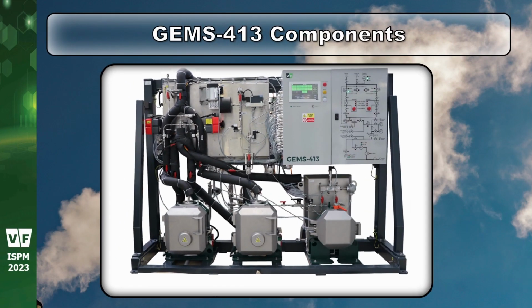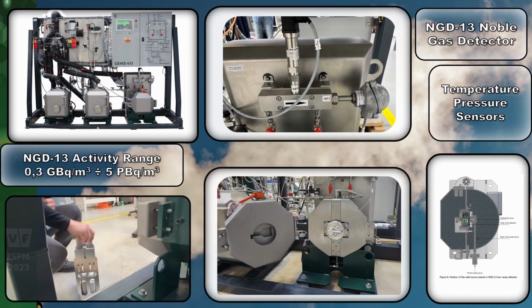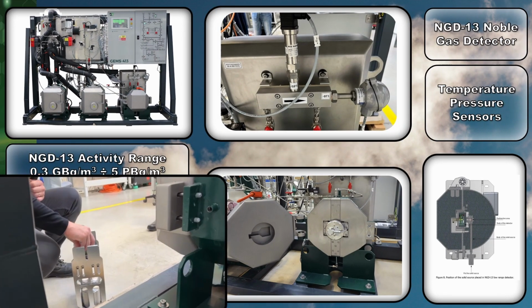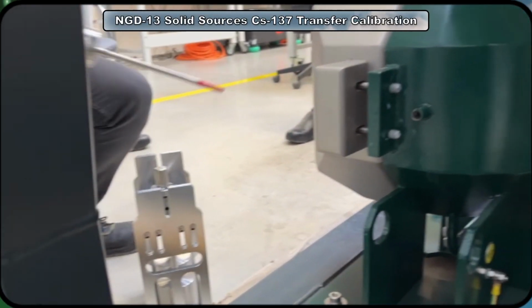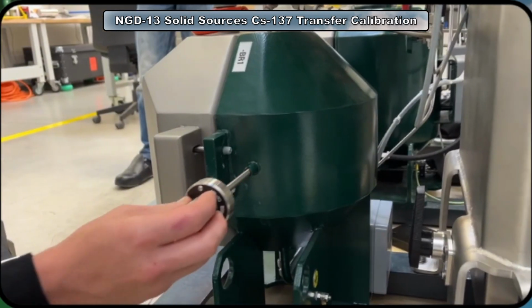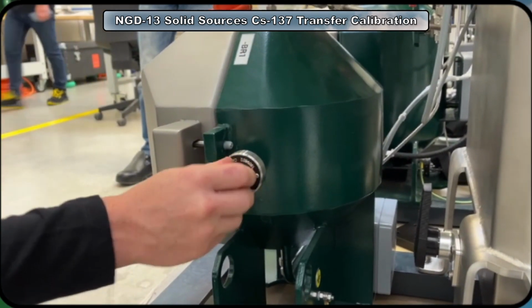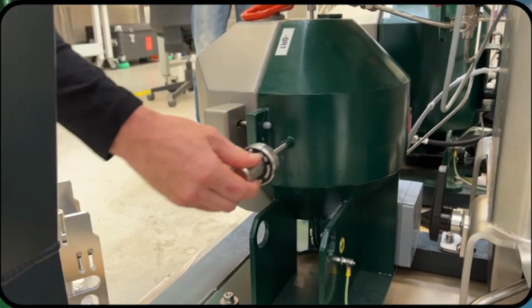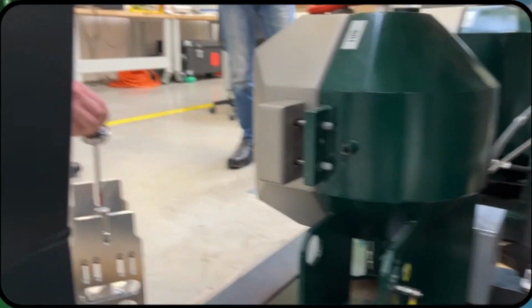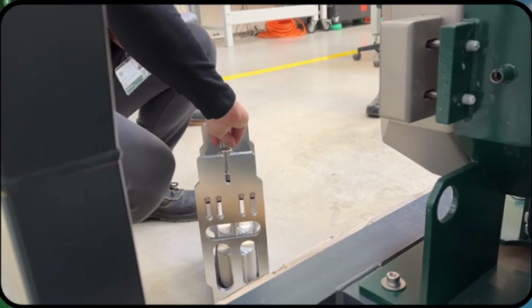The NGD-13 high-range noble gas detector with measuring range from 300 megabecquerels per cubic meter to 5,100 terabecquerels per cubic meter is used. Temperature and pressure sensors are used to recalculate measured volume activity to the standard conditions.